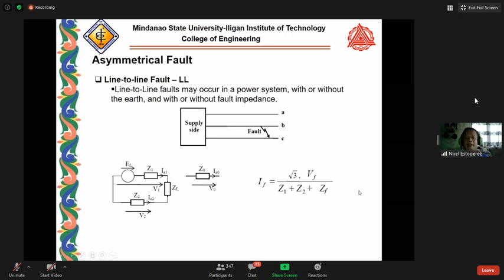If there is an existing fault impedance, this will be connected between V1 and V2. But when this ZF is 0, in the case of a line-to-line fault, the positive sequence network and the negative sequence network are in parallel. And this is IF, the fault current: square root of 3, my factor is square root of 3, Vf over Z1 plus Z2 plus ZF. So, this is the formula for the double line to ground fault.